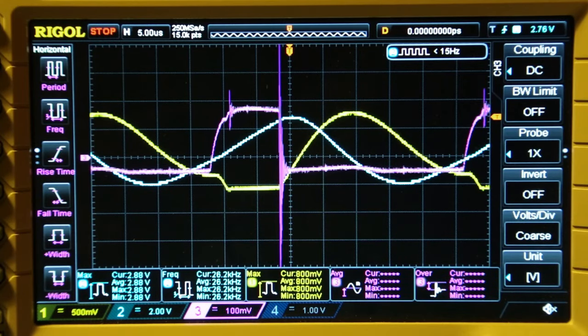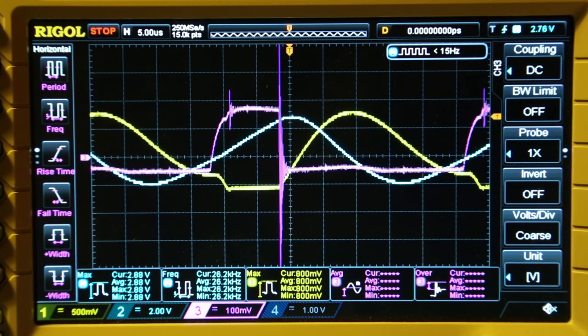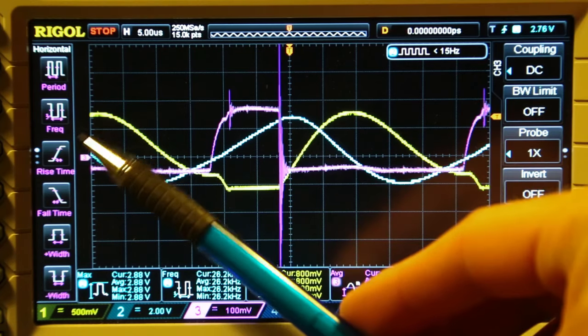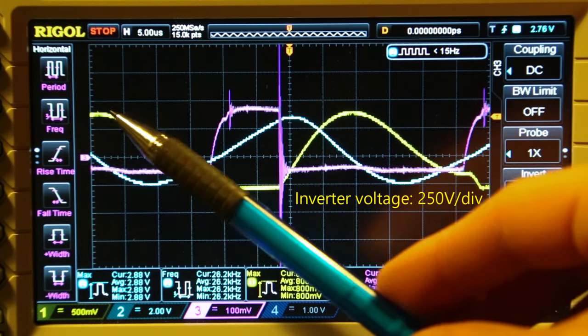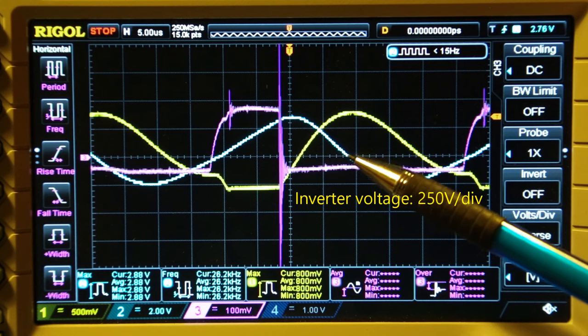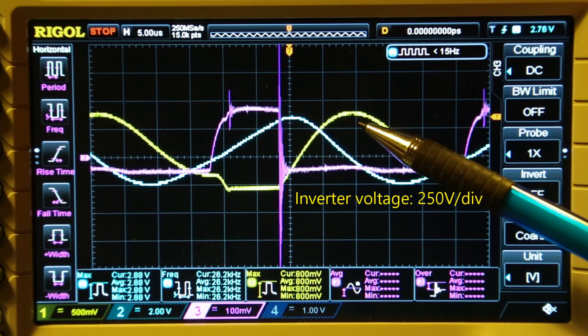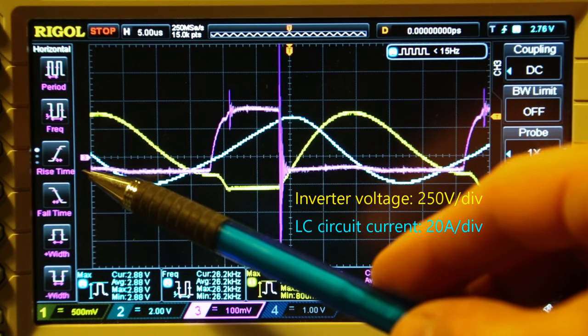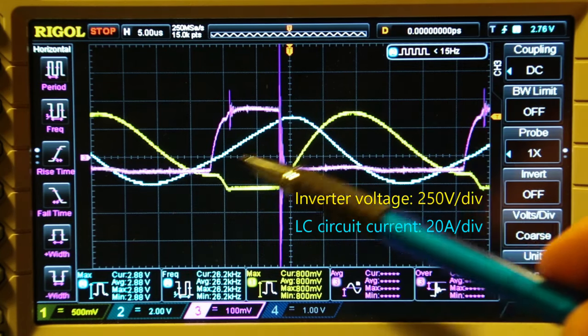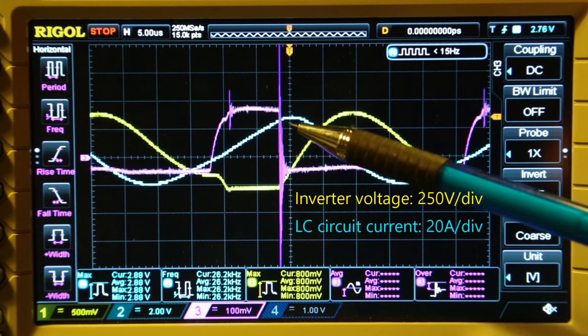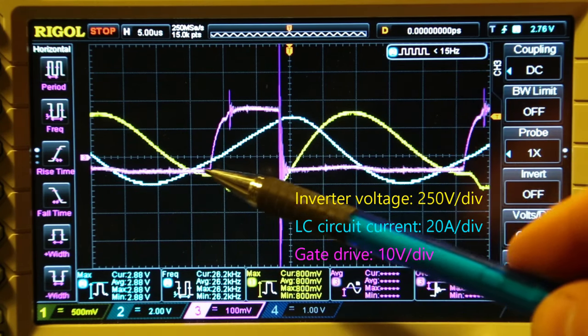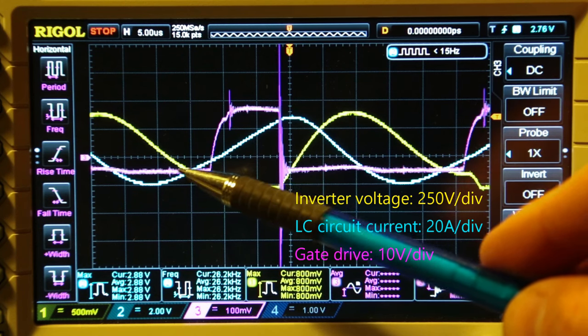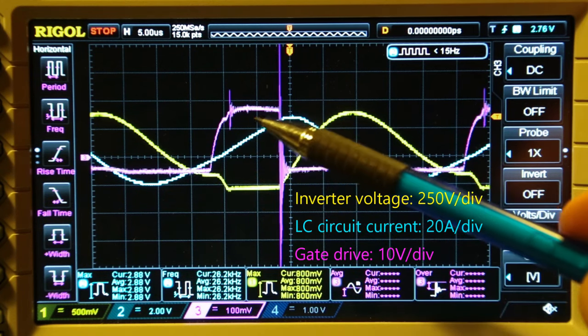So before we get started doing the measurements, let's first run through the oscilloscope setup. At channel 1, the yellow trace, we have the inverter output voltage. This is 250 volts per division. Channel 2 is the LC primary circuit current, the blue trace, at 20 amps per division. And we have the purple trace on channel 3, which is the gate drive waveform at 10 volts per division.